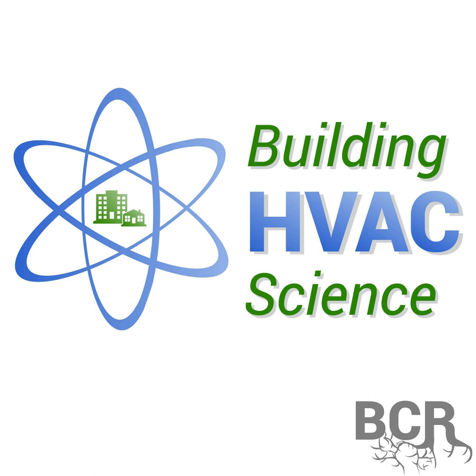Let's jump to another little topic here. Maybe little, maybe not so. You've got the supplies and returns set up, you're moving air, you're filtering it correctly. But what happens in, say, a retrofit where you don't have the right amount of air or the right air pressure in a room or a space? Like in a retrofit situation, if we need to deliver a certain amount of air, but we don't have a return duct, or we can't really get a return duct into that room.